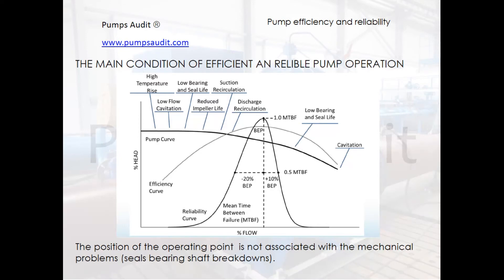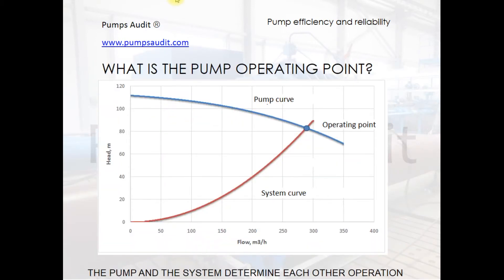This graph illustrates how the reliability of a pump depends on the position of the operating point, and what problems may arise when the operating point lies outside the operating range. If a pump breaks down, the pump user usually thinks the pump is of poor quality and that the manufacturer is responsible — not improper pump operation. The pump operating point, or duty point, is the intersection of the pump curve and the system curve, meaning the pump and the system define the operation of each other.